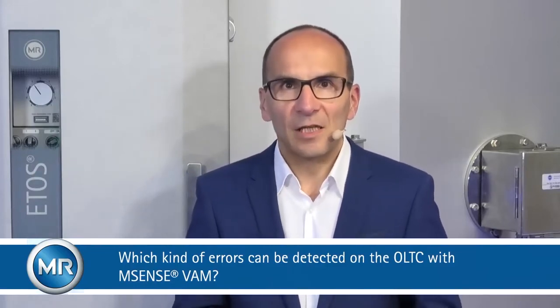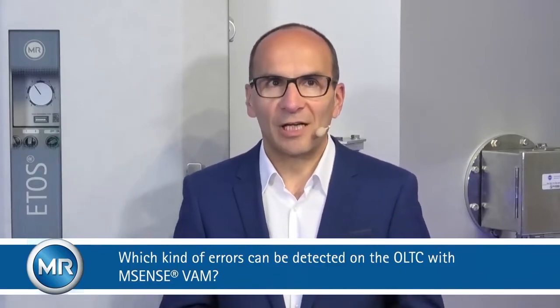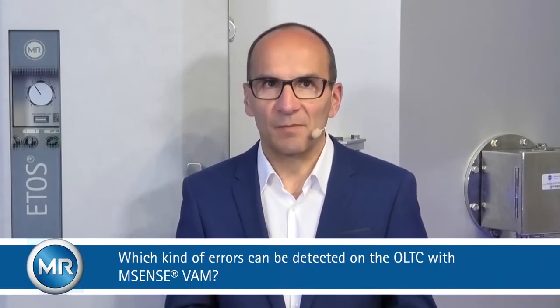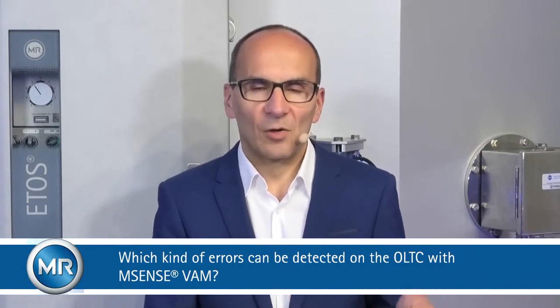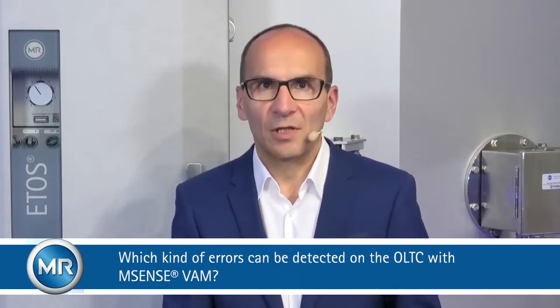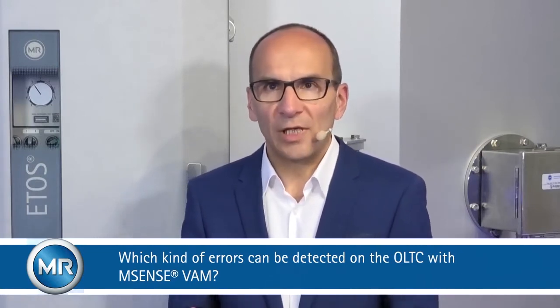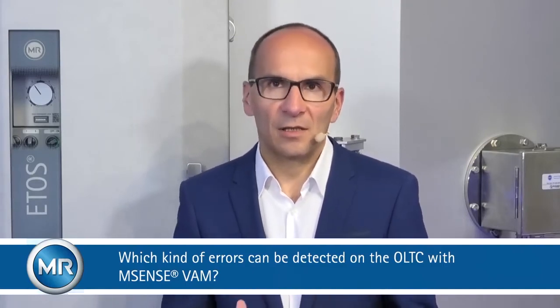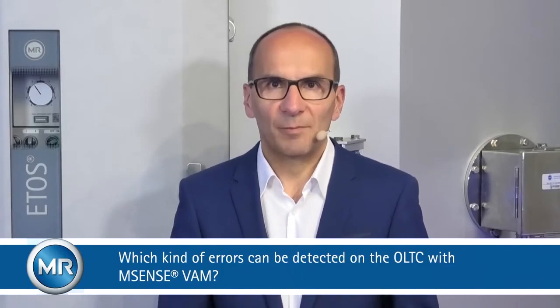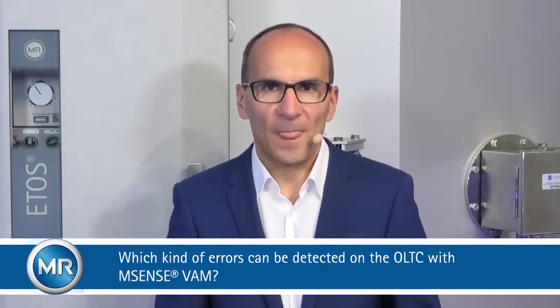That's one aspect which can be detected with online VAM. The second is really if we look at online VAM as a monitoring system. A monitoring system allows you to detect three types of errors. One, slow moving changes in the timing and in the vibration sound pattern of the OLTC.